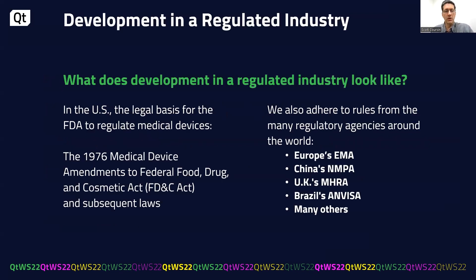So what does development in a regulated industry look like? I cannot hope to convey all of the issues surrounding this in such a short talk, so I will stick to the basics. In the US, the Food and Drug Administration regulates all medical devices, and the law breaks down into the Code of Federal Regulations. Many other countries and regions have regulatory agencies — Europe has the European Medicines Agency, China has the National Medical Products Administration, and so forth. For brevity, I will use the FDA terms for the rest of the talk, but keep in mind that similar regulations exist throughout the world.